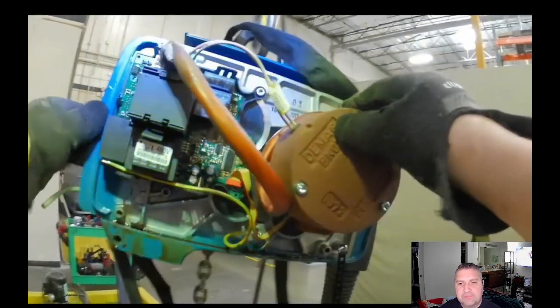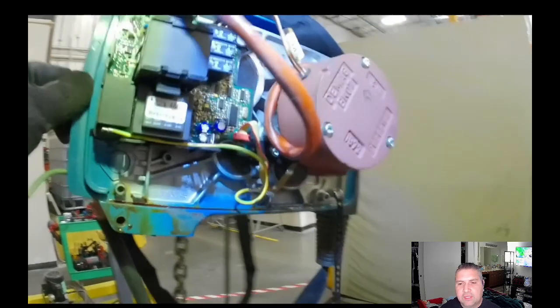So that's pretty much it. That one was kind of a fun one. And that troubleshooting process, every situation is different, but that's basically it. In these cases, I just removed the load, tested it with no load, did some references based on their schematics and their troubleshooting methods from the manual, and that led me in the direction. But yeah, if you ever have trouble with these hoists, man, your meter is your best friend.